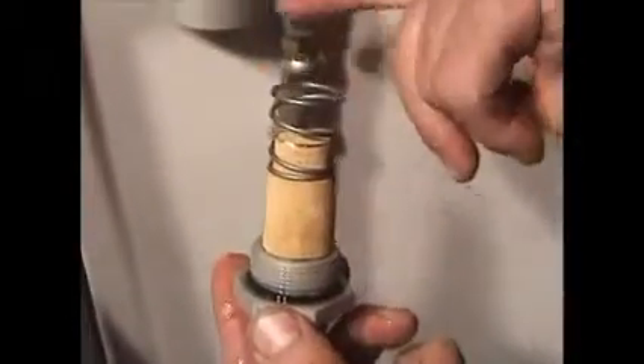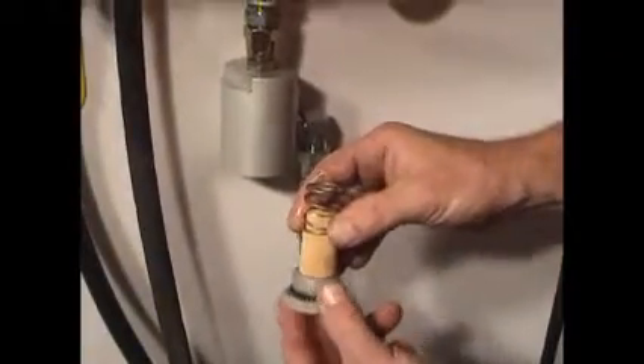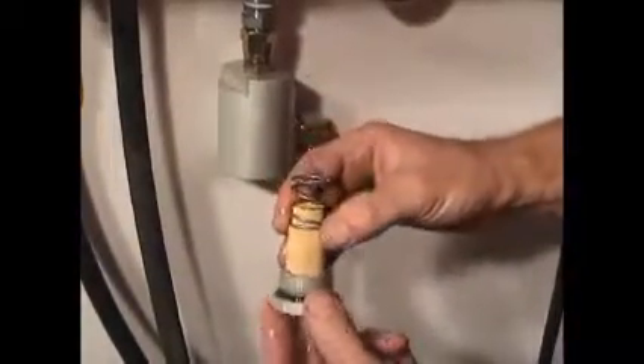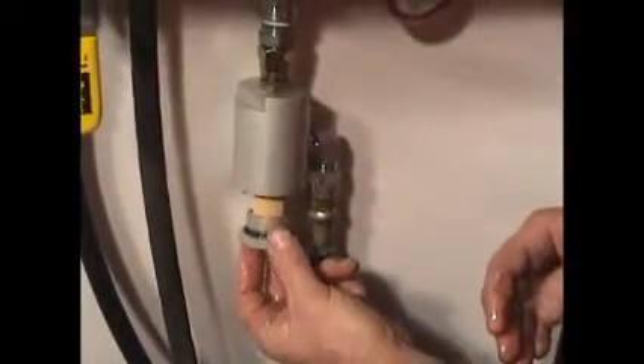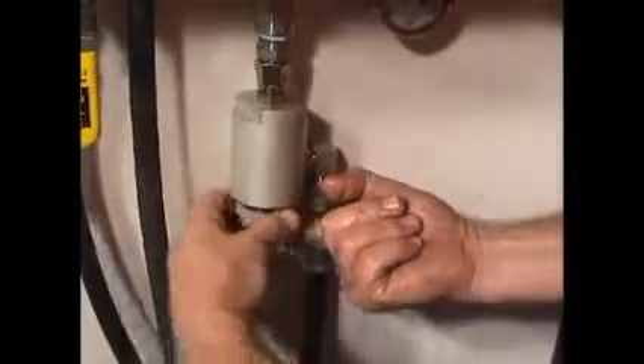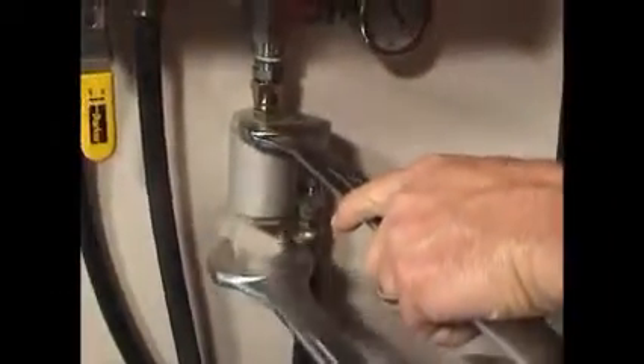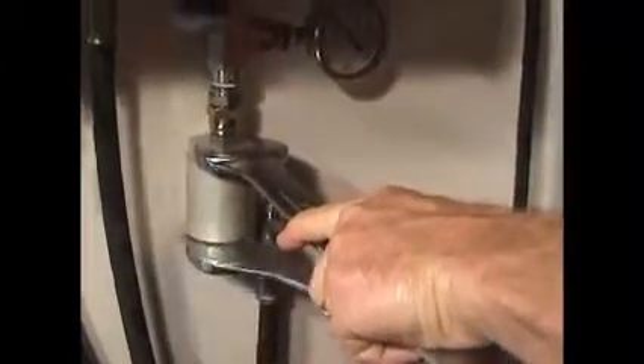Make sure the O-ring on the cap is in good condition. There's also an O-ring on the inside of the element. Make sure that that one is also in good condition. Both this O-ring and the inside O-ring come as a kit with the element, so they are with the element for replacement. Simply slide the element back in place and start the threads and retighten. After the filter has been hand tightened, finish tightening the plug till just snug, and that's all there is to changing it.